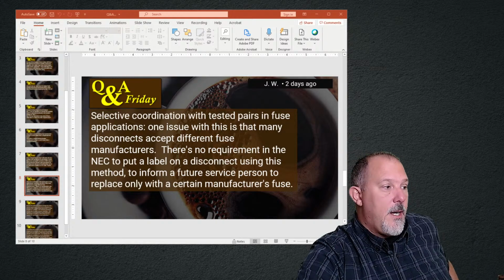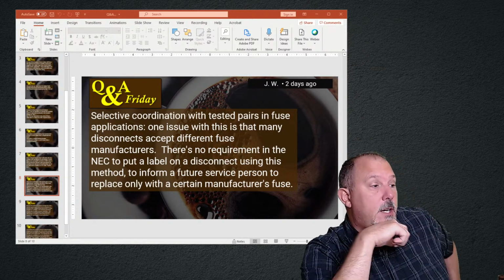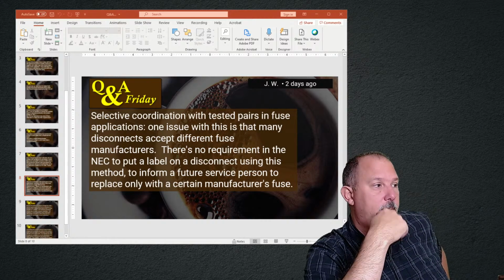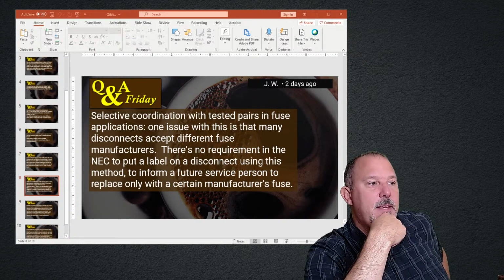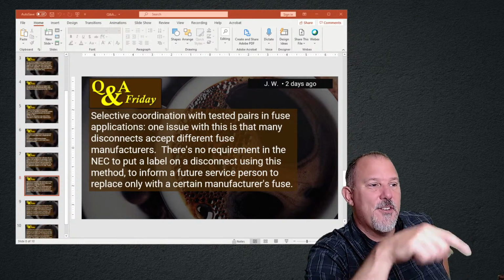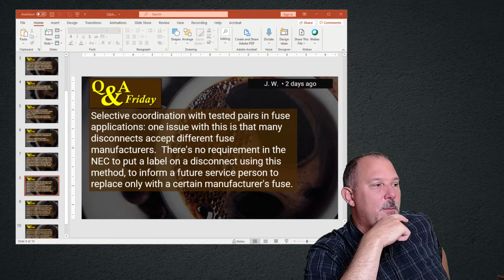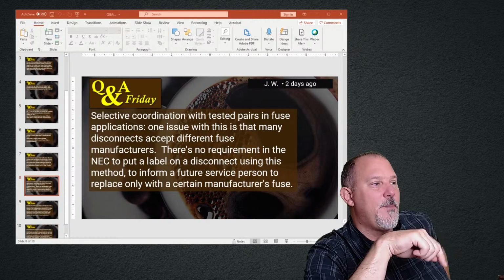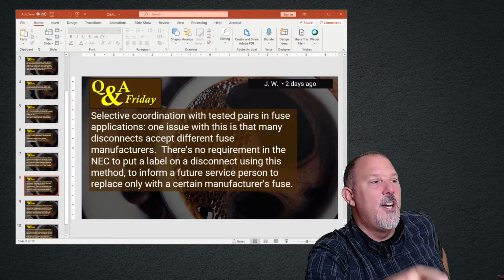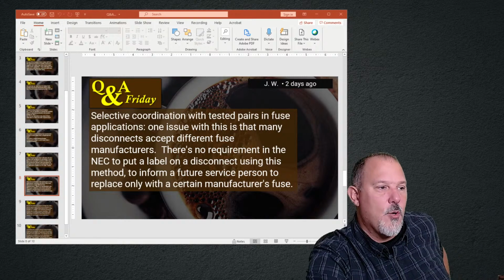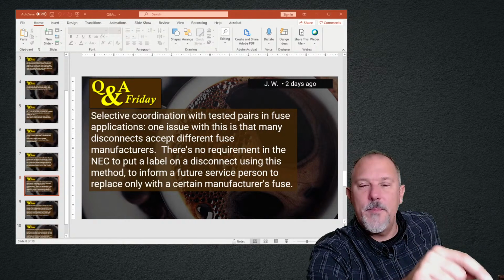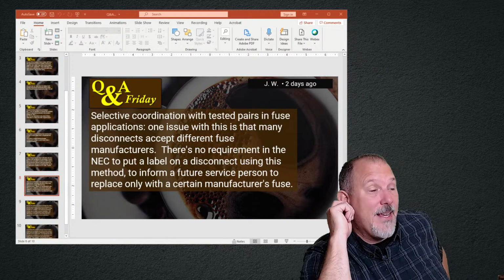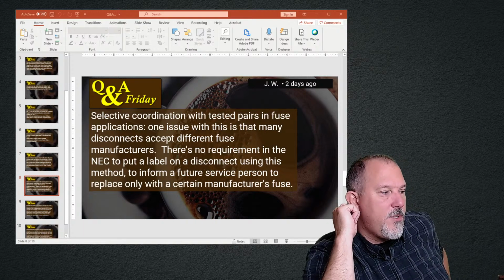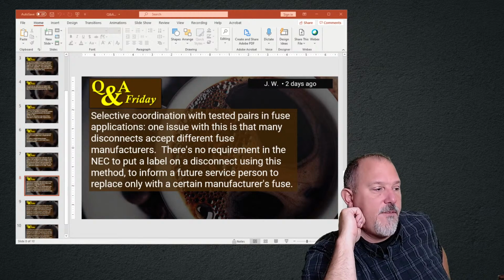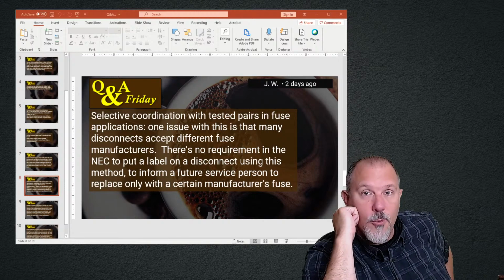Oh, yes, look. Michael Dempsey from Trinity Code Inspections put a public input in that said, equipment enclosures for selectively coordinated overcurrent devices shall be legibly marked in the field to indicate the overcurrent devices are selectively coordinated. The marking shall meet the requirements of 110.21(B) and shall be readily visible and state the following: Caution, overcurrent devices in this enclosure are selectively coordinated. Equivalent replacements and trip settings are required. I like that.